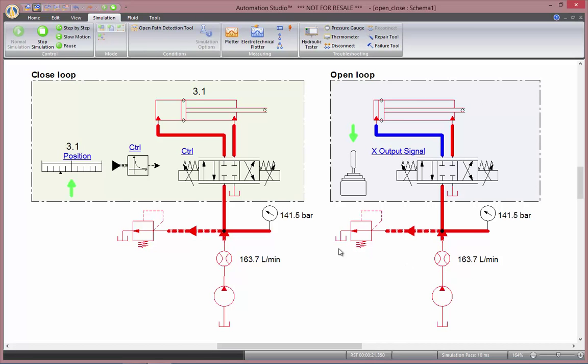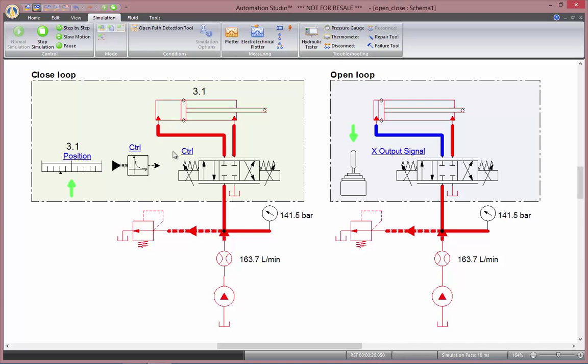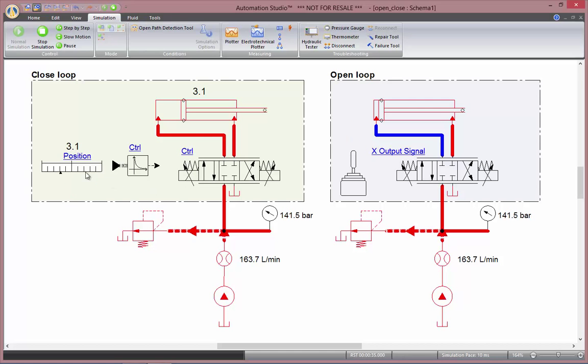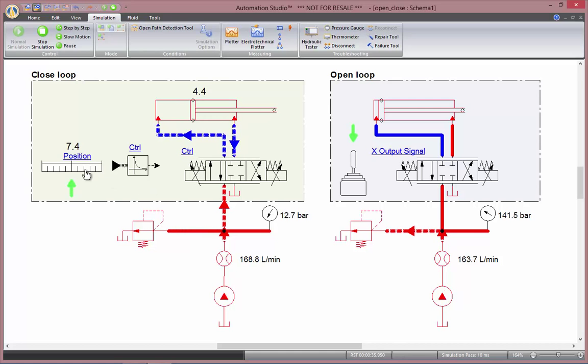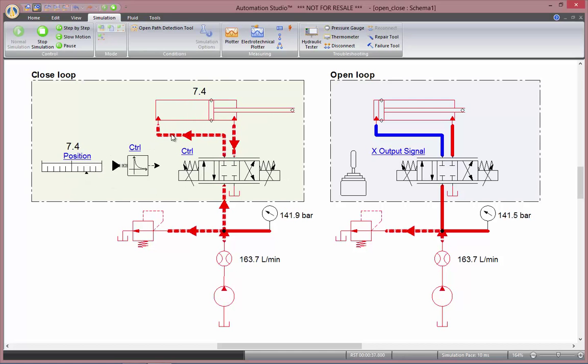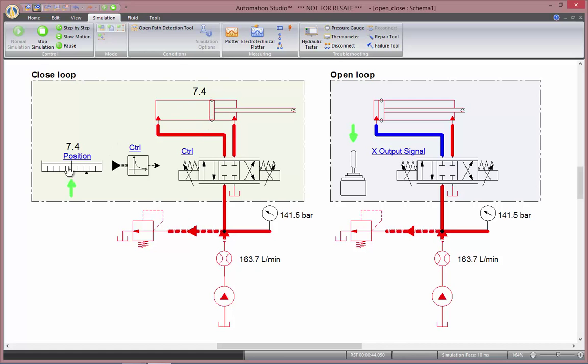On my closed loop here, I have a controller that compares the signal and the position and then sends the signal to the directional valve to correct the error. If I ask position of 7.4, the command will be given in order to have a final position of 7.4.